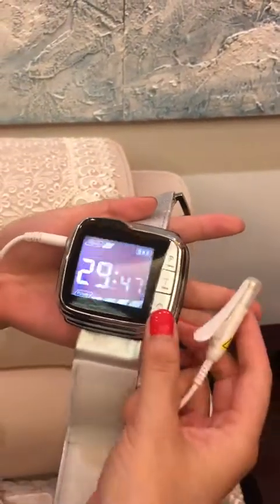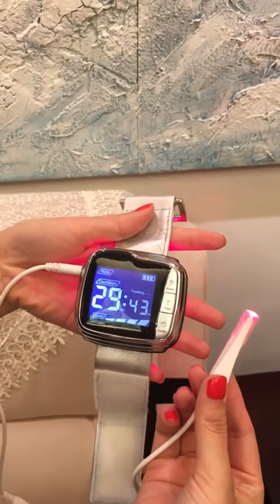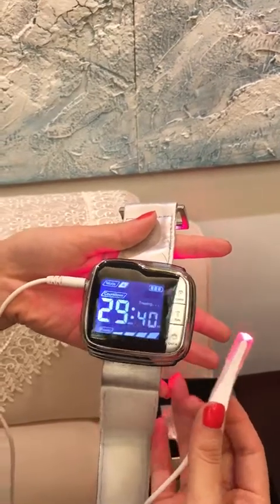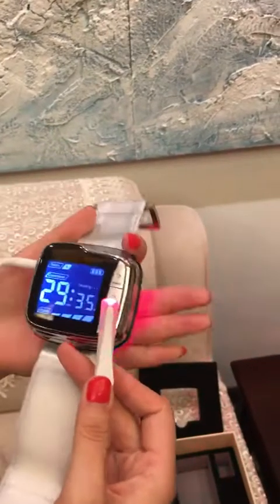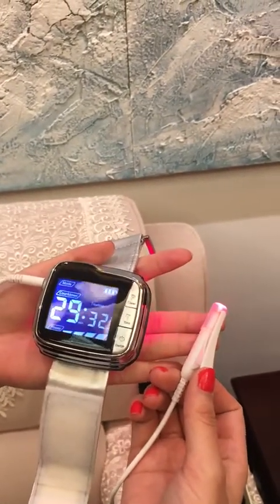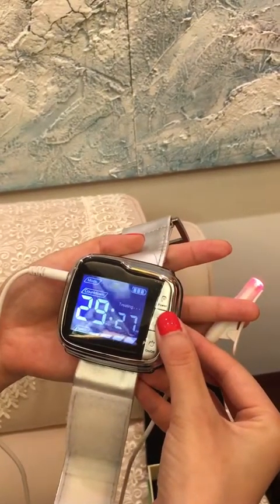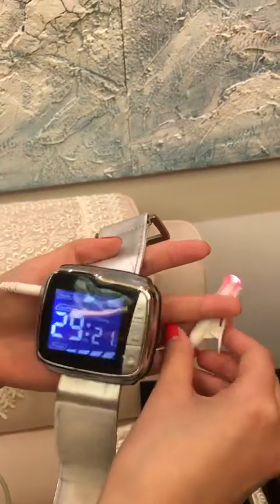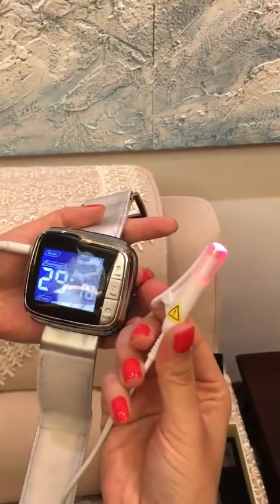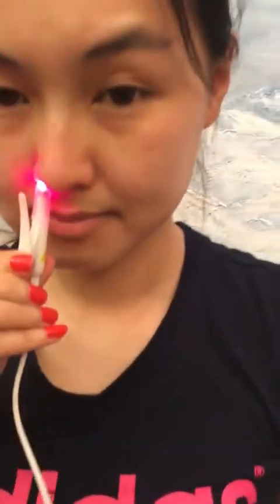Press the switch button. Both the host and the laser cavity probe are now working — this is Mode A. Keep pressing the T button to adjust the mode; the LCD shows Mode B with the laser cavity probe working. We can put it into our nasal cavity like this — this is used for rhinitis.